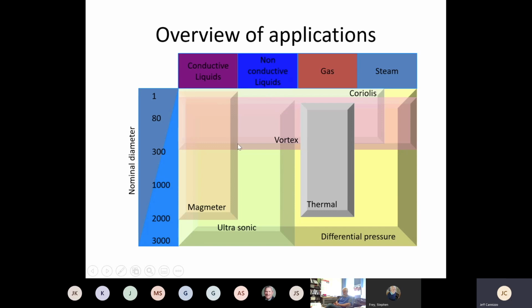Coriolis meters, again, liquid and gas and steam, a little bit limited on temperature. So it can't take the high temperature steam, but Coriolis meters will work in all types of liquids and gas. Obviously, there's limits on size. Anybody that's priced up a 16-inch meter knows that they can get pretty expensive pretty quickly. Thermal mass meters, again, typically right here in clean gas, they can, because we can do insertion, they can handle some pretty big line sizes and duct sizes. And lastly, differential pressure really can be used in any area. Depends a little bit on the nature of how dirty the liquid is, but we can do differential pressure meters on slurries. You just have to take care with, obviously, the differential pressure transmitter selection and the connection to the meter itself.